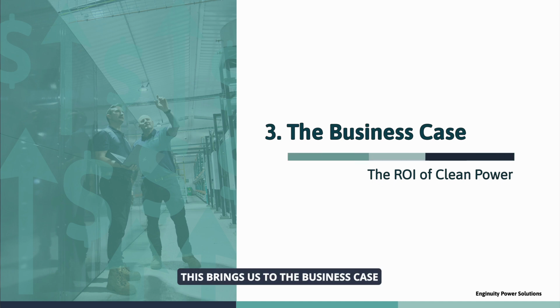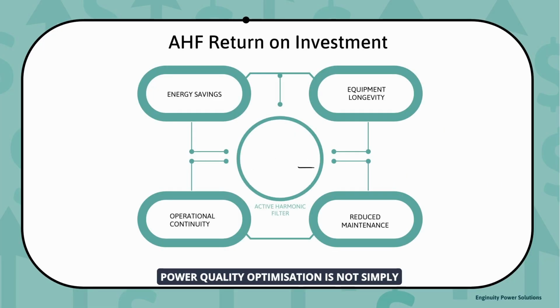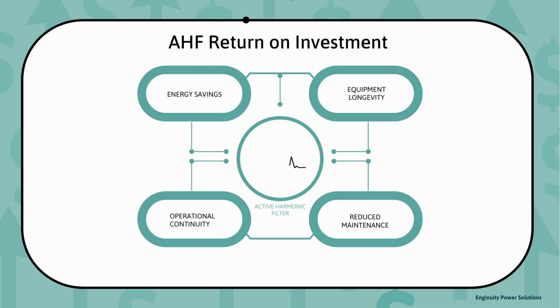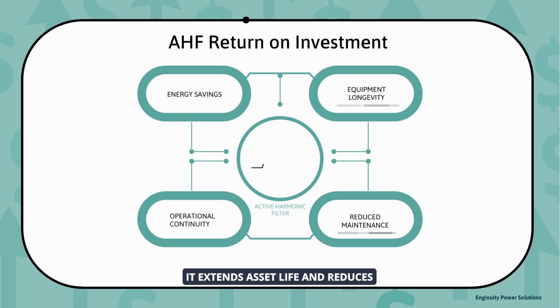This brings us to the business case. Power quality optimisation is not simply a compliance exercise. It is a measurable efficiency opportunity. Improved waveform quality reduces wasted energy. It lowers thermal stress on transformers and cabling. It extends asset life and reduces reactive maintenance. It can also reduce exposure to utility penalties linked to poor power factor or distortion. Most importantly, it reduces the likelihood of costly, unplanned outages. For many medium and large facilities, the return on investment is clear and defensible.